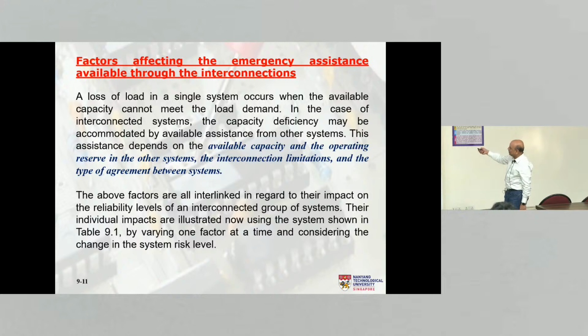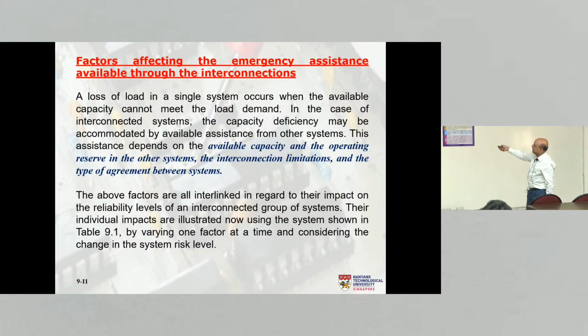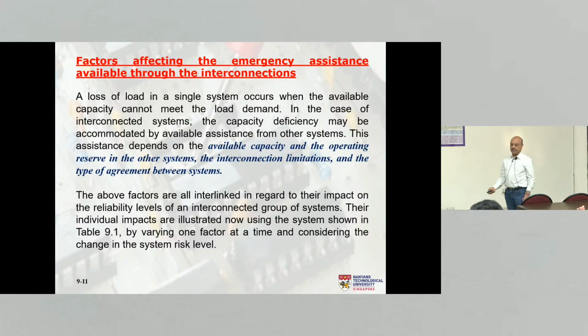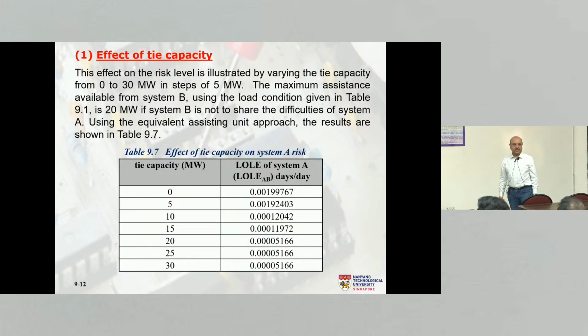So we have now seen that already when we connect the two systems, the reliability improves. We expected that to happen, okay? Now, this assistance depends upon several factors: available capacity and the operating reserve in the other systems, the interconnection limitations, and the type of agreement between systems, right? We can easily appreciate that. The above factors are all interlinked in regard to their impact on the reliability levels. So we'll consider them one by one, although they are interlinked. You can also consider them together, but it'll make the analysis more complex. So let's see the individual impacts. We start with the impact of tie line capacity first.